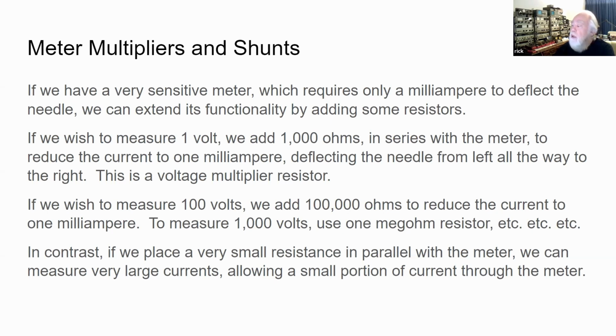Now, if we want to measure current, we don't want a large current through the meter itself. So we use a very small resistor that has a very small voltage drop when current flows through it, placed in series with the rest of the circuit, like when we measured current with the ammeter and the load. We place the meter element across that tiny resistor, which has only a small fraction of a volt even with 10 or 100 amps flowing through it. So we're reading a very small voltage, and we barely affect the circuit since we're adding only a minute amount of resistance, which doesn't change the current being measured.